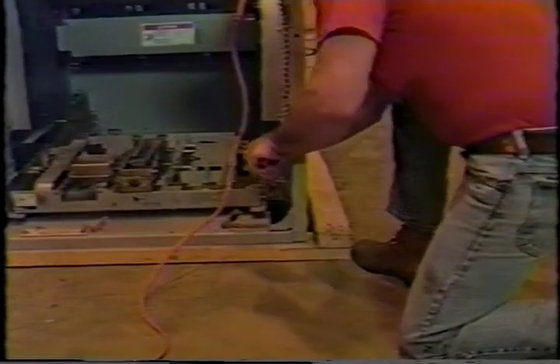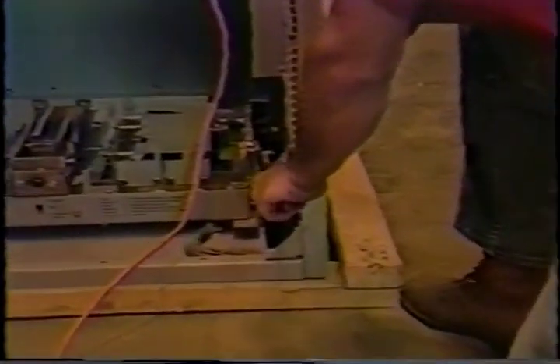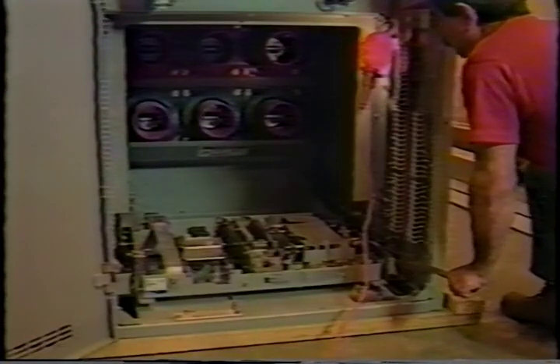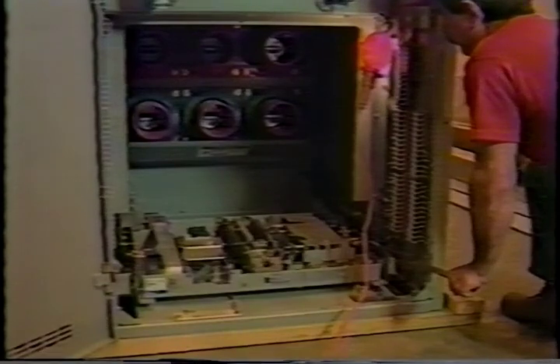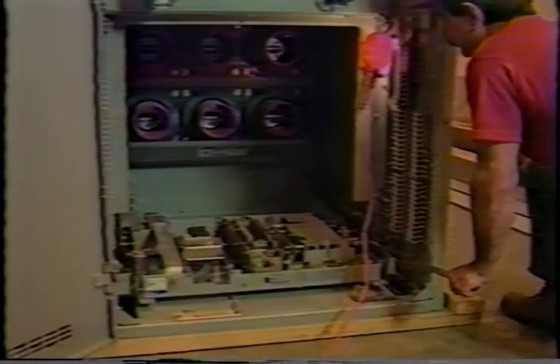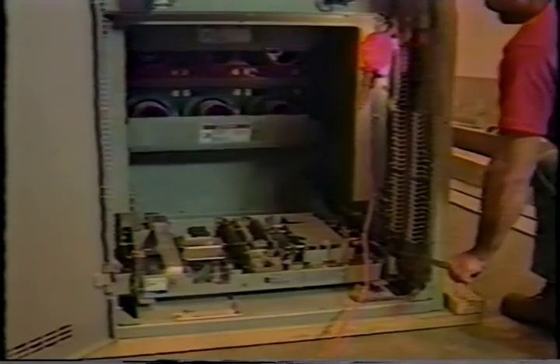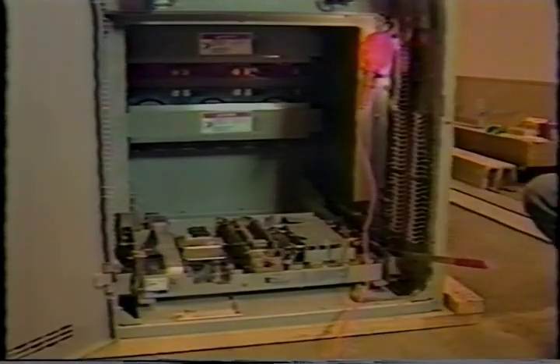Metal safety shutters automatically operate to restrict access to the breaker primary disconnects. A maintenance tool is provided to allow an operator to manually open the shutters for maintenance or inspection purposes. To prevent accidents or injury, these shutters should never be permanently blocked open.